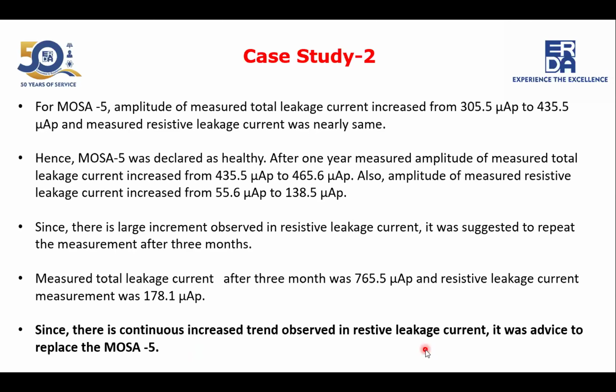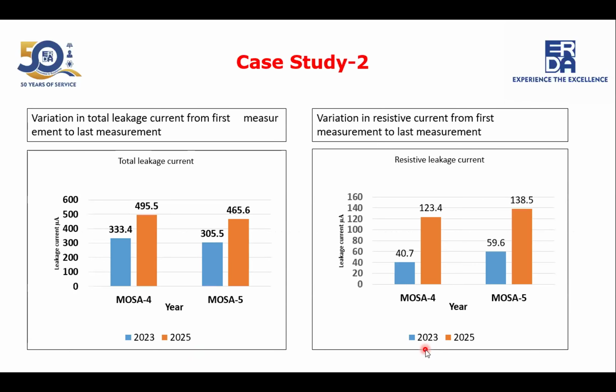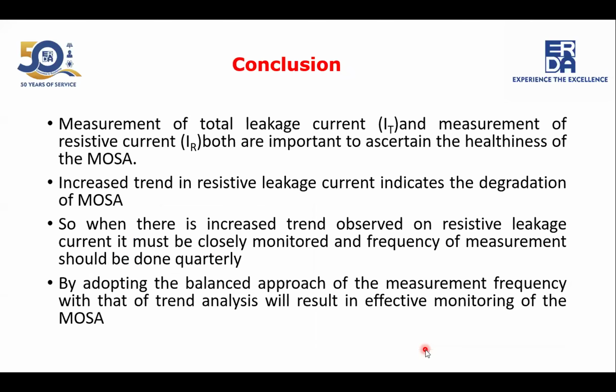So this is how we do the analysis of leakage current. We need to check both the total leakage current and the resistive leakage current, and based on that decide whether the surge arresters are healthy or not. If there is doubt, we repeat the measurement after a certain time, and based on that verify the healthiness of the surge arrestor.